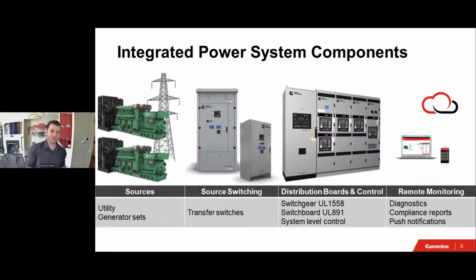So if you've attended some of my webinars, I always like to start with the basic components of a power system. I call those the pieces of the puzzle, right? So you have sources: that's a utility, a generator set that's diesel or natural gas, or it could be a renewable source. We'll have power switching equipment, commonly known as a transfer switch. And we have what's called distribution boards and system level control or supervisory control.